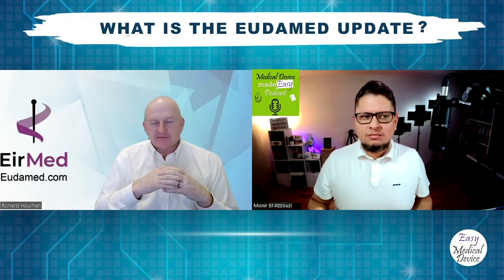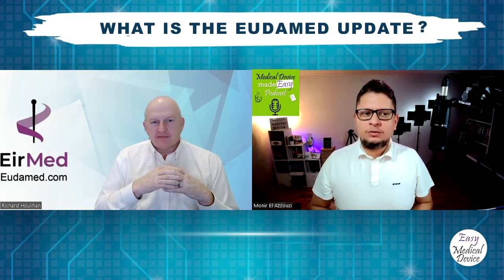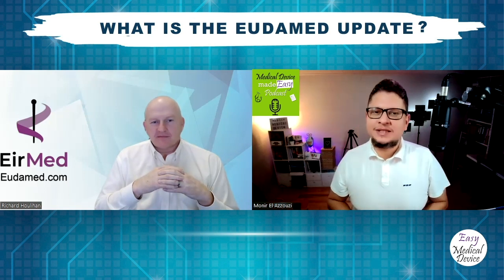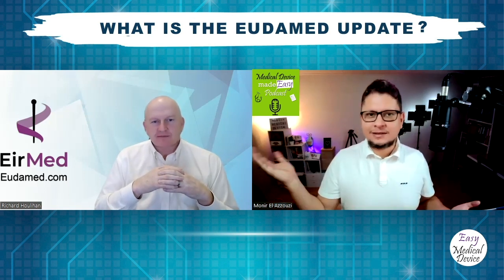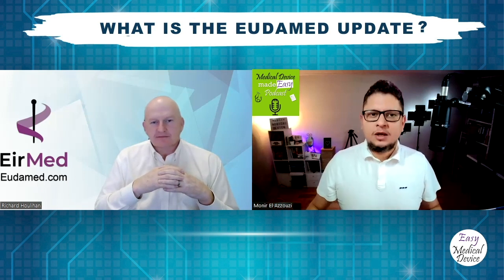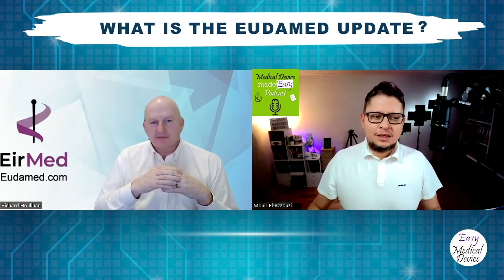So now I have a lot of people asking me, "Oh, how can I know if this product is really CE marked?" I say, for the moment, you cannot, but in future, you will be able to do that with EUDAMED when it will be fully authorized and mandatory for everybody. Then everybody will have to register their products inside. So there is no possibility for you to not know if this product is CE marked or not, because from class 1 to class 3, every product should be registered on the database.